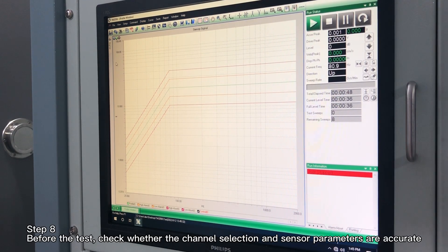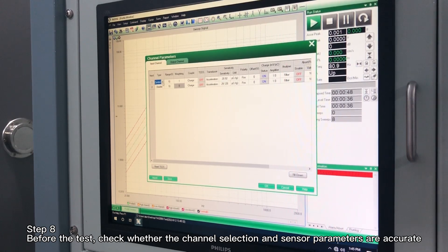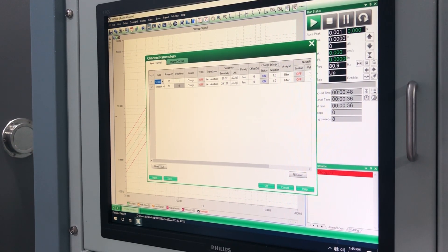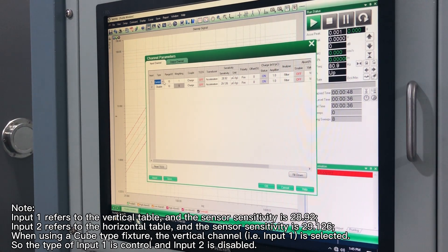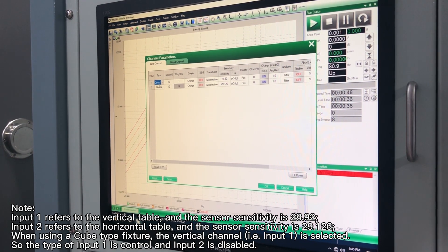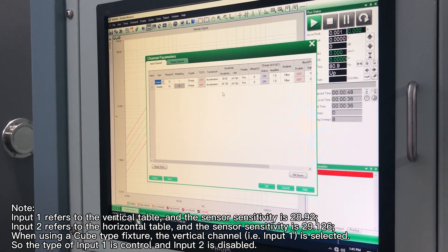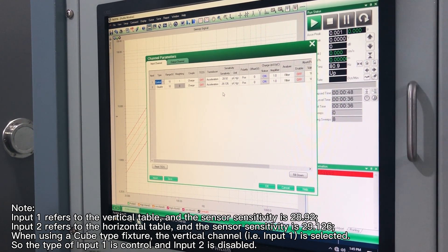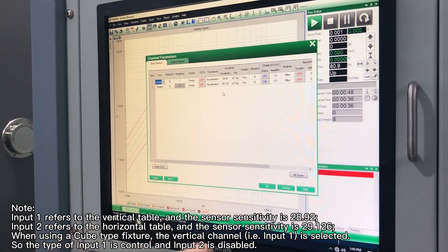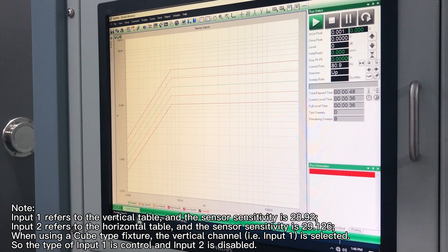Step 8: before the test, check whether the channel selection and sensor parameters are accurate. Note: input 1 refers to the vertical table and the sensor sensitivity is 28.92. When using a cube type fixture, the vertical channel input 1 is selected, so the type of input 1 is 'control' and input 2 is 'disabled'.